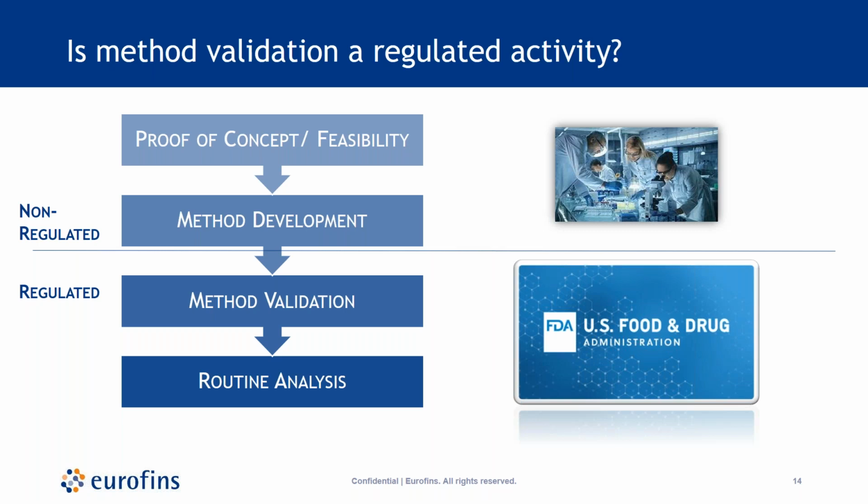And then when you hop into the method validation process, that is going to be regulated. Document validation plans, including acceptance criteria. You need to define those acceptance limits and system suitability. Perform the evaluation experiments, including robustness, and document all of this in compliance with the applicable regulations. All of this will be under QA oversight, and really can't be hidden from the regulatory process. Routine analysis as well, method transfers, define the document and process review cycle, monitor performance, maintain adequate change control, and perform regular process inspections.